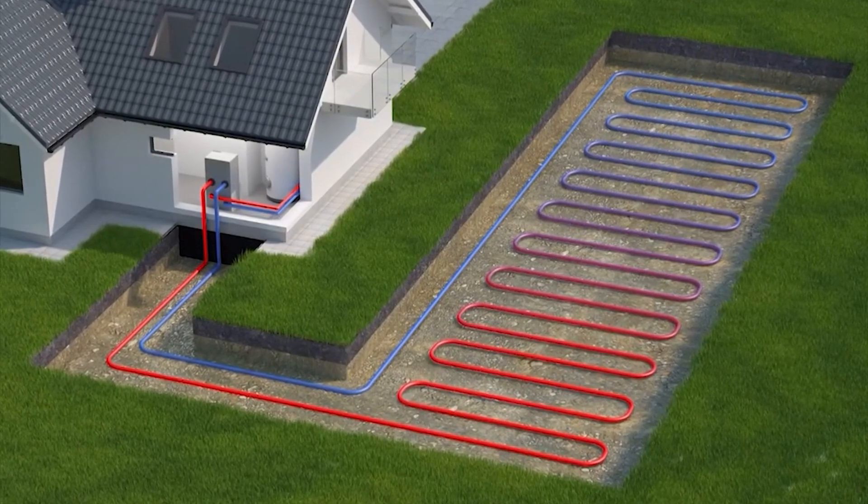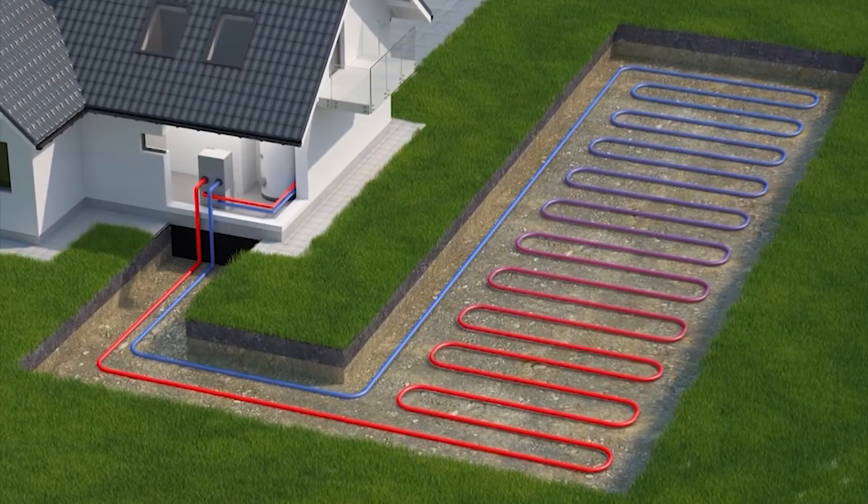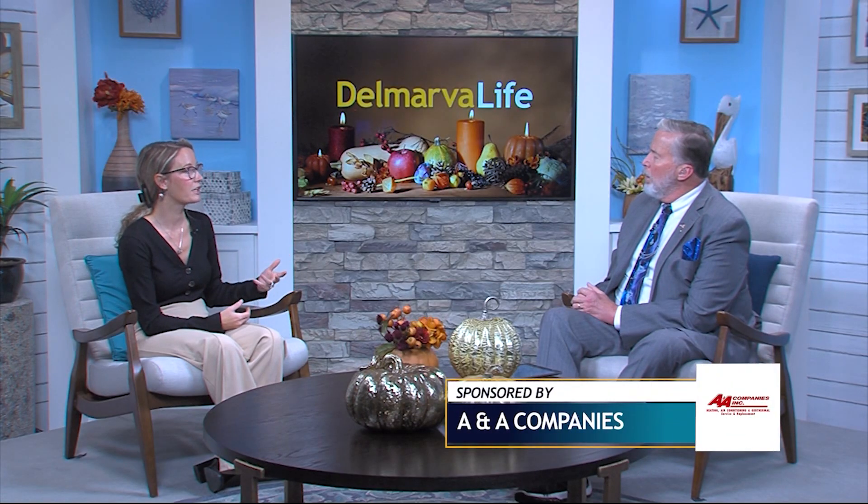When it comes to the quality of your air, does geothermal improve it? A geothermal system is going to provide you the same type of heat or air conditioning that a heat pump does. The benefit is it's not subject to outside air, so it's not going to call for backup heat. Geothermal systems only call for backup heat if there's a problem or if you increase the temperature on your thermostat drastically. I've had geothermal in my house for almost 15 years and my systems have only ever called for auxiliary heat twice — both times because of a failure. They are much more reliable than a heat pump when it gets cold, and they won't run constantly in air conditioning mode because they're not pulling in 100-degree outside air; they're utilizing the ground's constant temperature.